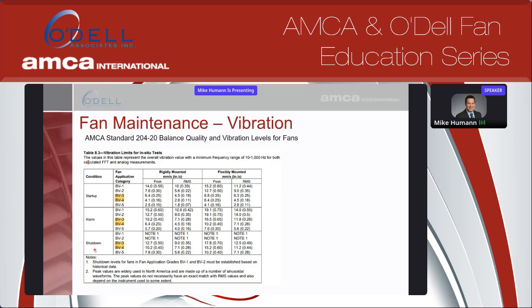And typically in the fan industry, both industrial and commercial, you see BV3 and BV4 as the typical fan application categories. So you tell the fan manufacturer, I want this fan at BV3 or BV4. That way it leaves the factory at that level, and then out in the field, you should see similar levels. And this is the data you can see.